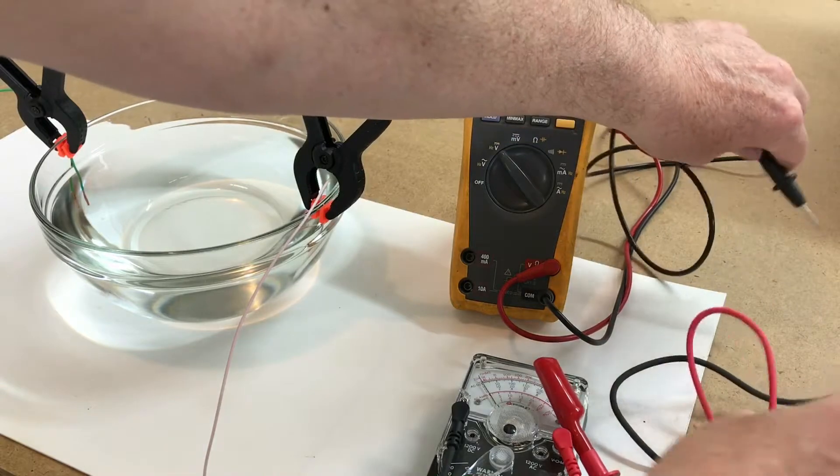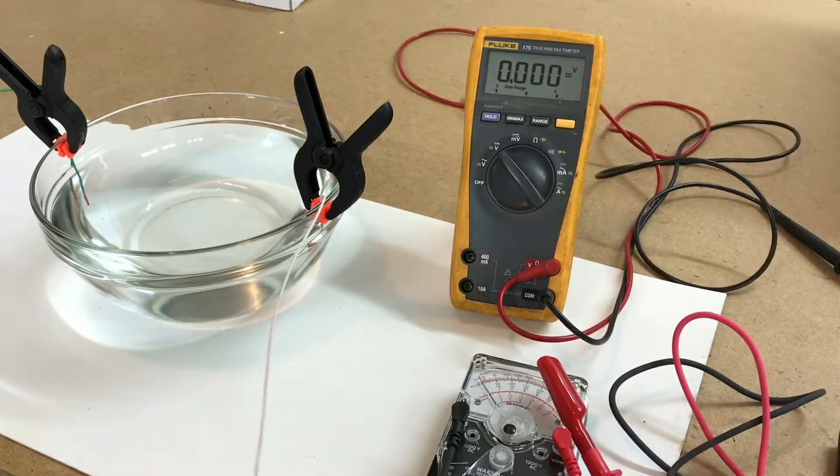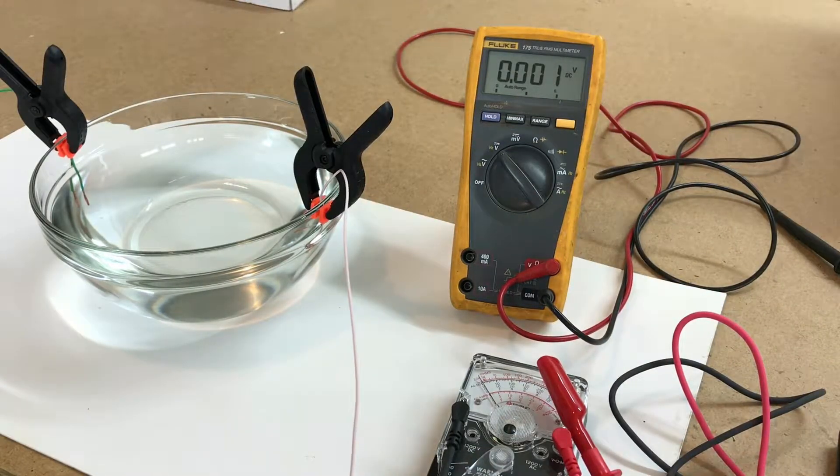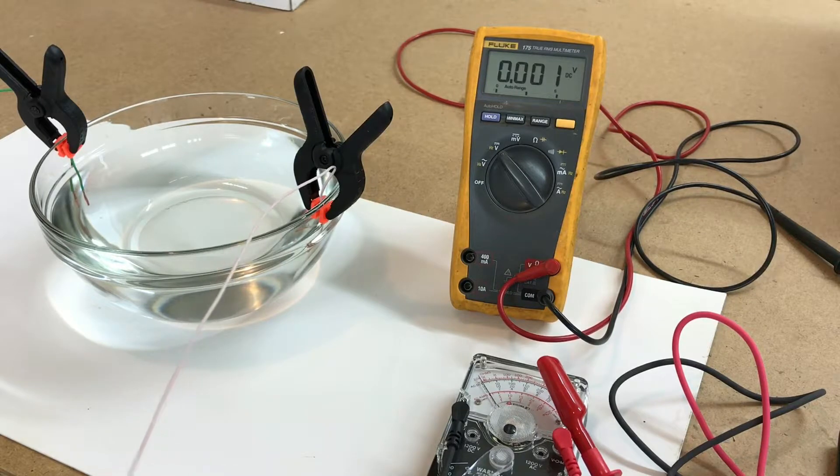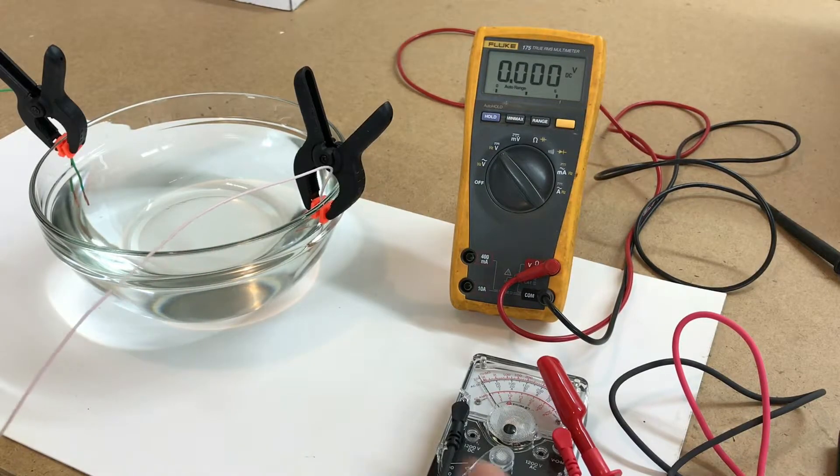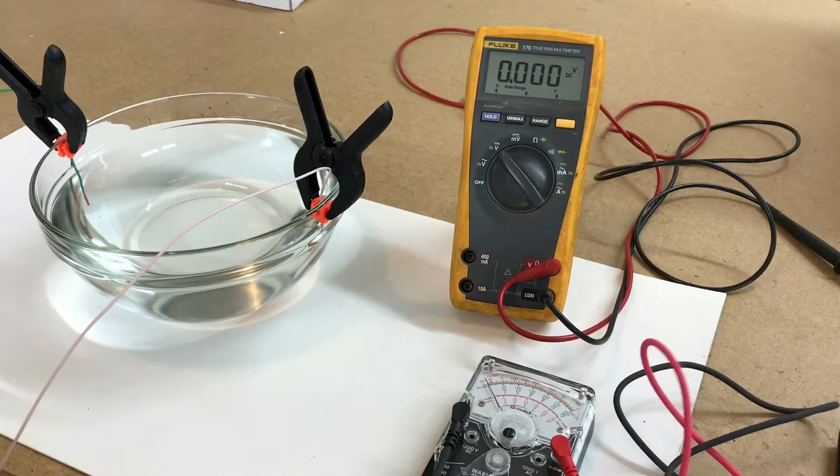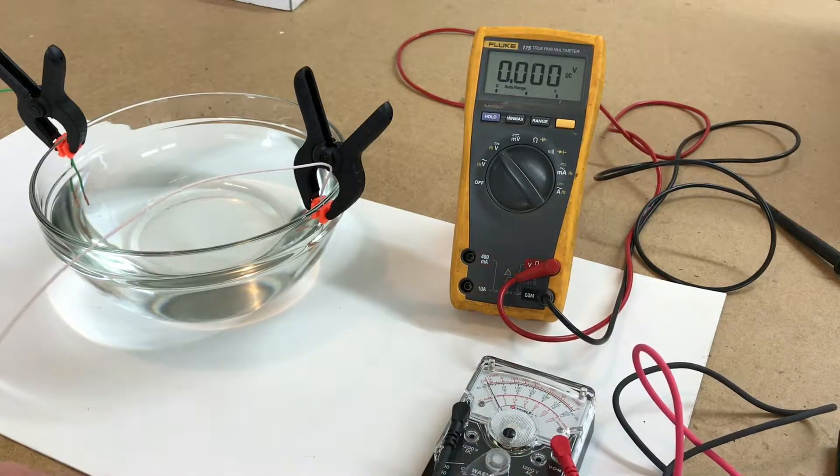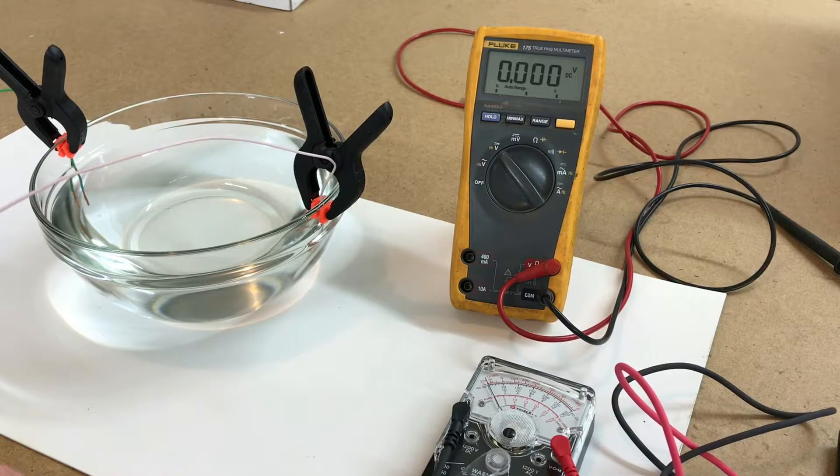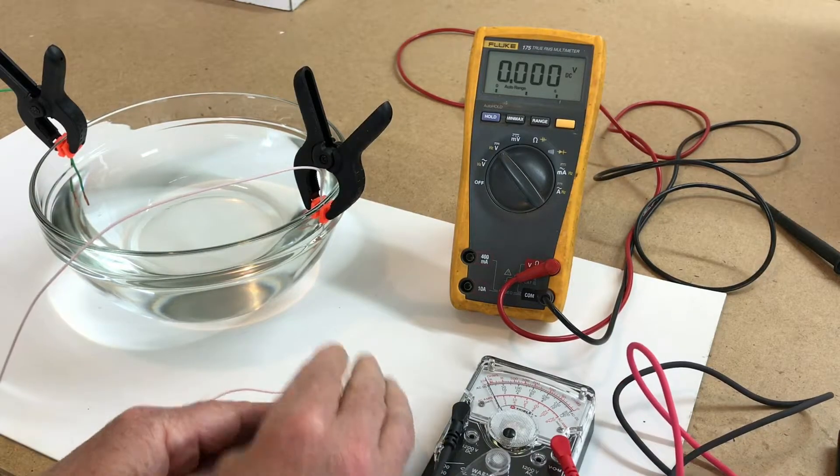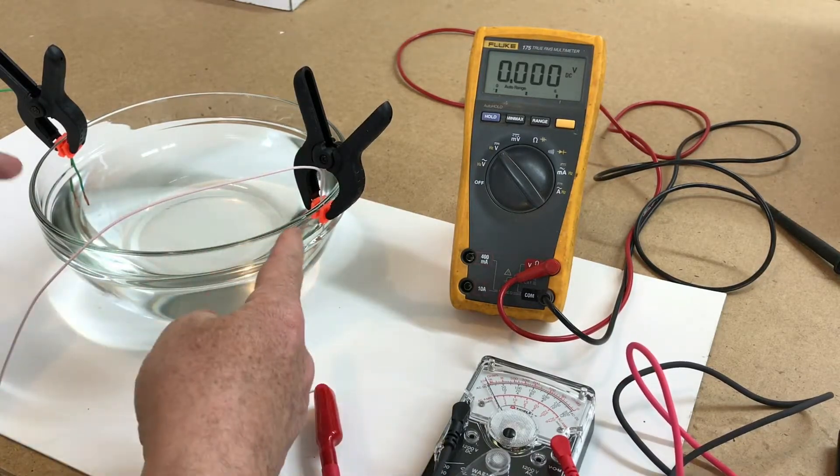So a good example, I got a little mock-up here. A lot of ground faults on fire alarm panels happen with water in junction boxes or devices. That's a high resistance ground because the circuit is being made through the water. If we take the meter and I got the wires in the water on both sides of the bowl.